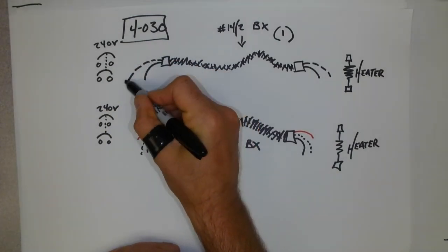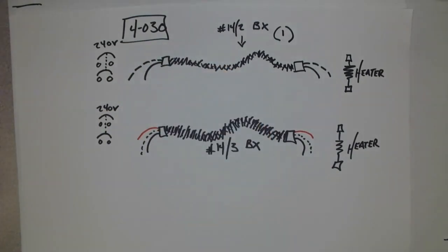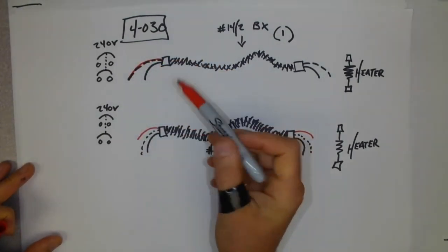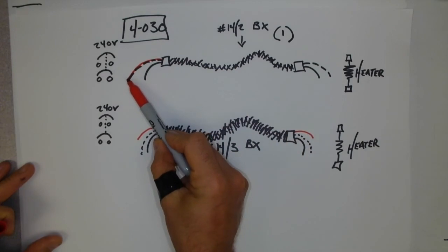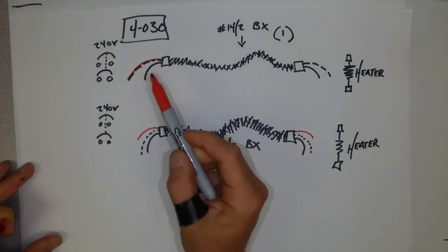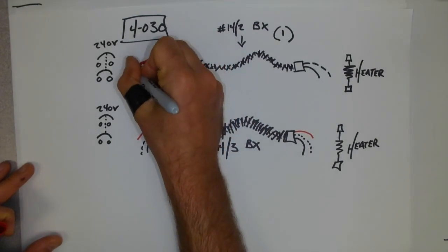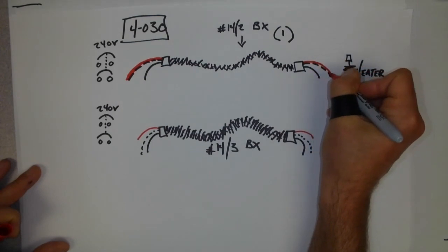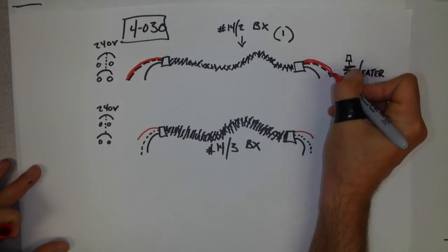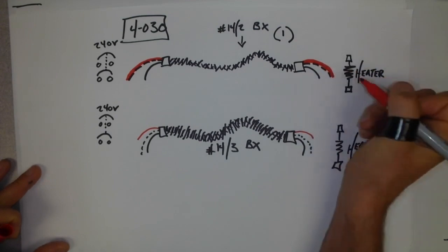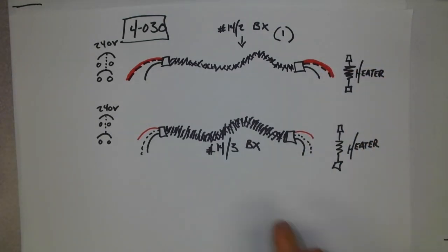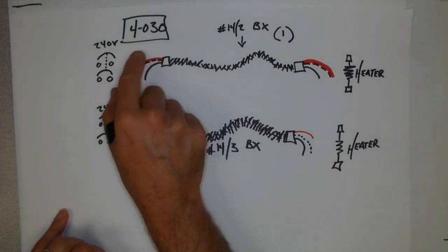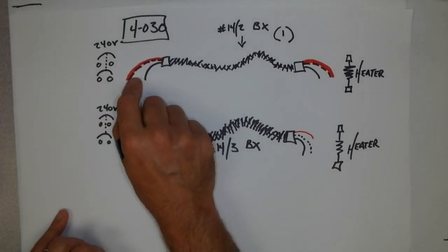But for most of us, we know that we're going to use phase tape. And you could then phase tape it red because the color coding for a 240-volt circuit is red and black. So red phase tape would really be the alternative here. So I phase tape the white conductor red. And what that does is it makes it very obvious to everyone who's in the panel that this is a 240-volt circuit and that someone hasn't just accidentally hooked the white wire up to the breaker.